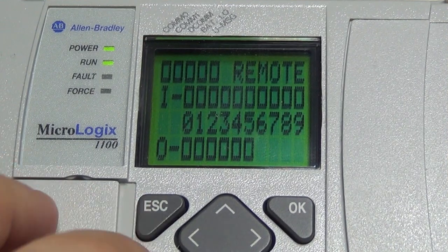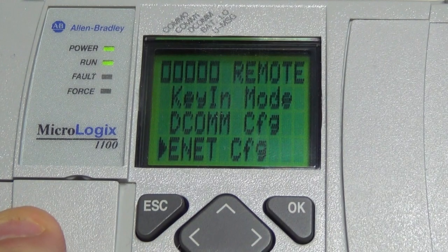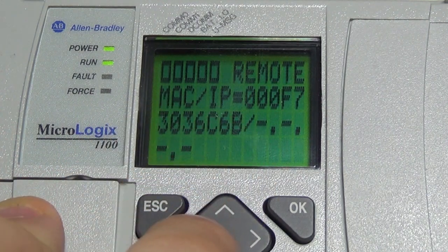The first question you need to ask yourself is whether or not the PLC has already been initially configured. A PLC out of the box will not have an IP address set, so in order to connect you'll either have to go through an ethernet cable or a USB cable, then use the BOOTP utility or RSLinx to set that initial IP address. On the Micrologix, if you hit escape and scroll down to advanced settings, then ethernet configurations, you will see the MAC address but no IP address yet. If there is an LCD screen it should give you an IP address; if not, you need to set one.